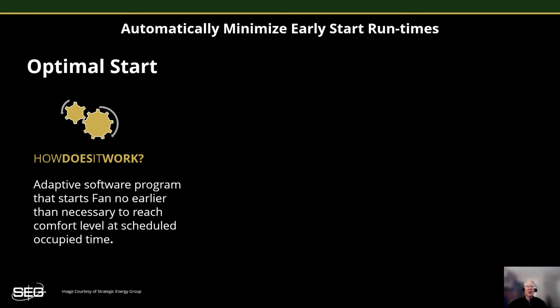It's the amount of time that the equipment will need to start early, and it will vary seasonally as well as day to day depending on the outside air temperatures. Now, many savvy building operators understand this, and they adjust the HVAC equipment start times seasonally to try and match the early start period to the seasonal temperature swings. Now, this is a step in the right direction, but there's a much better way to achieve a comfortable building by occupancy time while still eking out greater savings on a daily basis. And it's called Optimal Start.